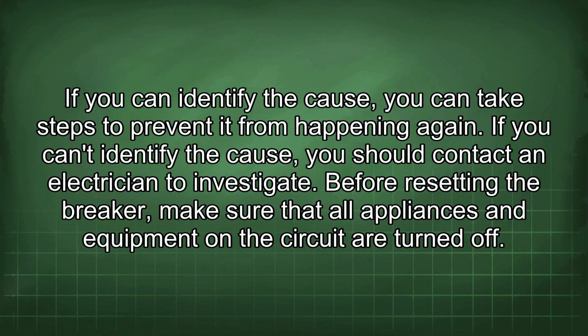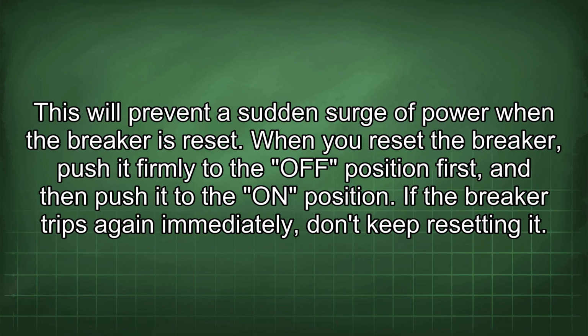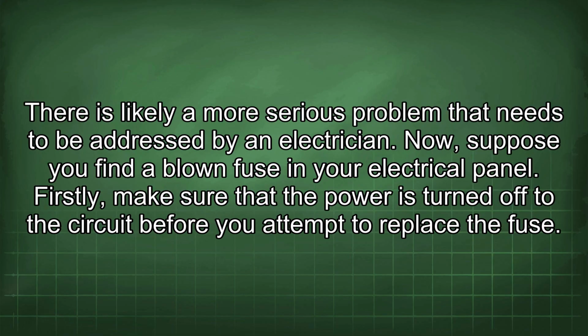Before resetting the breaker, make sure that all appliances and equipment on the circuit are turned off. This will prevent a sudden surge of power when the breaker is reset. When you reset the breaker, push it firmly to the OFF position first and then push it to the on position. If the breaker trips again immediately, don't keep resetting it. There is likely a more serious problem that needs to be addressed by an electrician.